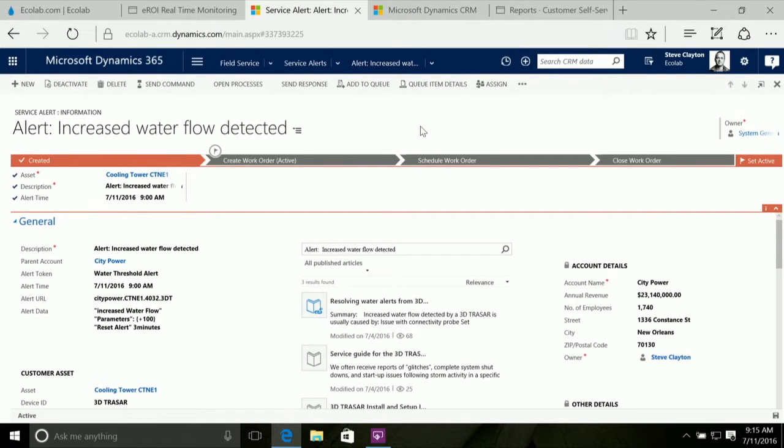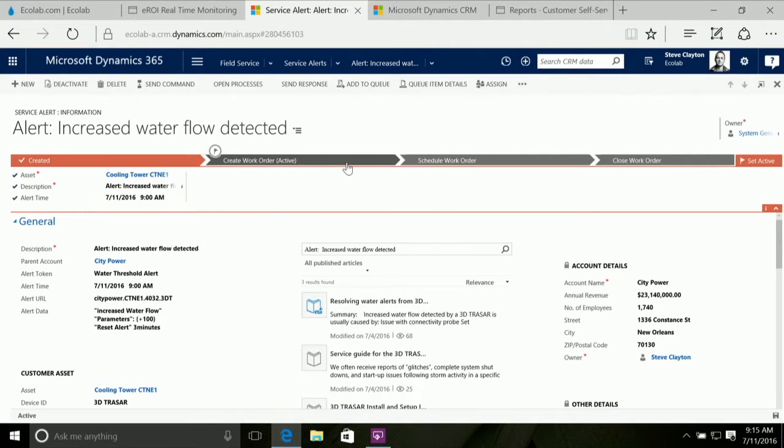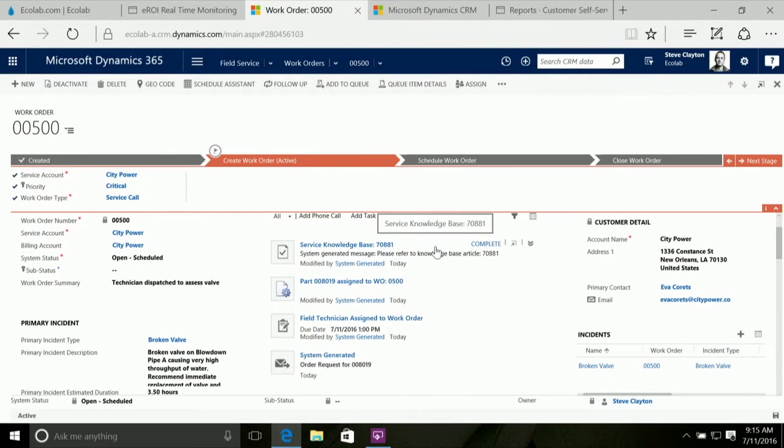We can do that directly from the service issue. If I choose to send a command using Azure IoT Suite, this is literally sending a command down to the 3D TRASAR sensor in that cooling tower to see if we can resolve the issue. It turns out the probe is operating correctly, but there seems to be an issue that requires a manual inspection. So now we're going from remote interrogation to a whole work order being created. Four things have happened automatically: we've assigned a field technician based on their expertise, their location, and the availability of the part they have in their van to resolve this issue.